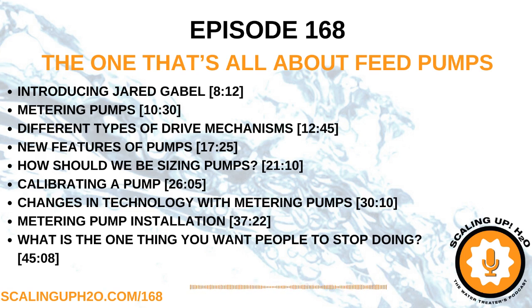You mentioned different types of drive mechanisms. So you said peristaltic, diaphragm, I believe you said piston. What are the differences between those? Why would you choose one over the other? Historically, what we're seeing is either you're drawing chemical into the pump from a suction lift application, where I have to pull it up several feet into the dosing head, or I could also have a flooded suction application. There are also chemicals that are readily off-gassing, like sodium hypochlorite and other acids that want to be a gas. So anytime you get air inside of the dosing head or allow that to happen, then you have a situation that allows you to vapor lock the pump.